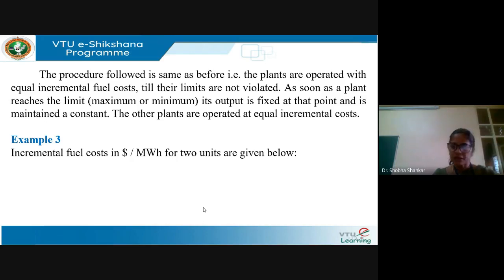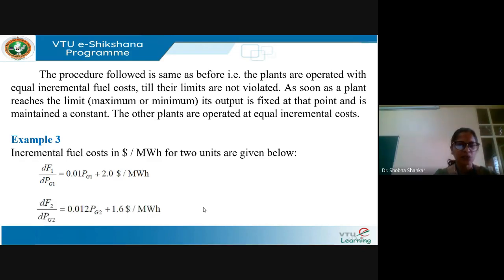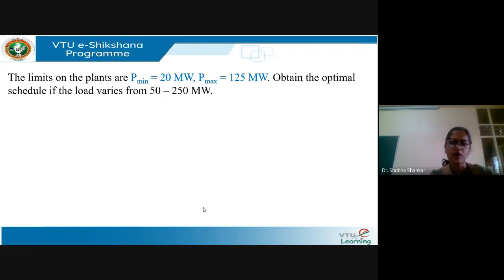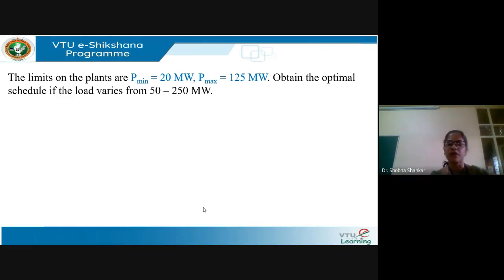The incremental fuel cost in dollar per megawatt hour for two units are given. For the first plant: dF1/dPG1 = 0.01·PG1 + 2 $/MWh. For the second plant: dF2/dPG2 = 0.012·PG2 + 1.6 $/MWh. The limits on both plants are: minimum 20 MW and maximum 125 MW. We need to obtain the optimal schedule if the load varies from 50 MW to 250 MW, minimizing total fuel cost.